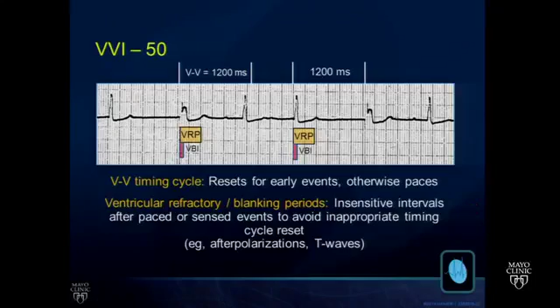I doubt that it'll be on the boards, but be aware of the existence at least of a so-called ventricular refractory period and ventricular blanking interval. These are intervals during which the ventricular sensing of the device is off, so that the device will not have inappropriate resetting of the time clock in response to things you're not interested in seeing the time clock reset for, such as electrical afterpolarizations or the T wave. But certainly if you have a PVC that occurs very early during the refractory period, it will not reset the time clock, and that's a nuance of VVI operation that can sometimes be confusing.